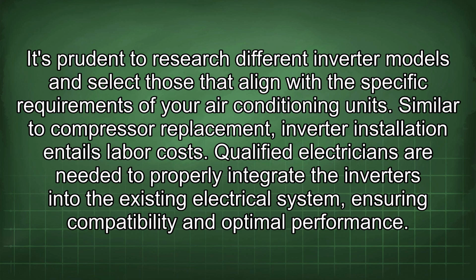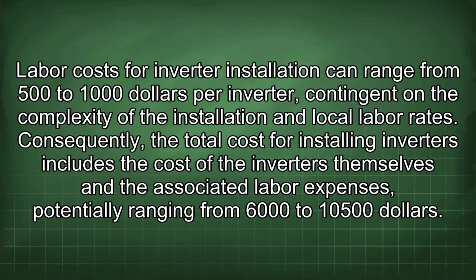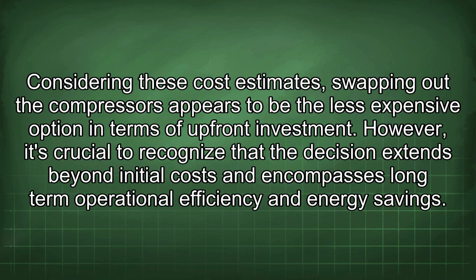Similar to compressor replacement, inverter installation entails labor costs. Qualified electricians are needed to properly integrate the inverters into the existing electrical system, ensuring compatibility and optimal performance. Labor costs for inverter installation can range from $500 to $1,000 per inverter, contingent on the complexity of the installation and local labor rates. Consequently, the total cost for installing inverters includes the cost of the inverters themselves and the associated labor expenses, potentially ranging from $6,000 to $10,500. Considering these cost estimates, swapping out the compressors appears to be the less expensive option in terms of upfront investment.